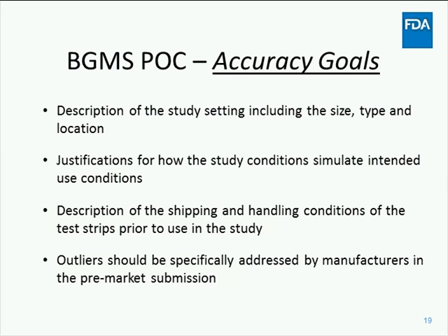In cases where data points fall outside of these accuracy goals on the previous slide, a clinical justification should be provided in the pre-market submission for each of these data points, along with a description of any other proposed mitigations. And as described in the draft, the study should be accompanied by a description of the study setting, including the size, type, and location of the site, provided in the pre-market submission, along with a justification for how the study conditions represent the intended use conditions. The patient demographics should be described, including the age, disease states, and any medications that each study subject may be on, along with a description of the shipping and handling conditions of the test strips prior to use in the study.